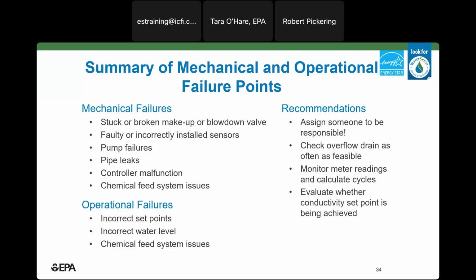On the operational side, common failures include establishing incorrect set points at which the system should be blown down. Similarly, the level sensor in a tower could be installed incorrectly, leading to the tower underfilling or overfilling. The chemical feed system can be programmed incorrectly to apply too much or too few chemicals. Those are just a few examples. And most of these things can be pretty easily identified and resolved just by making sure that staff is assigned responsibility for the cooling tower and understands the basics of what's going on in the system.